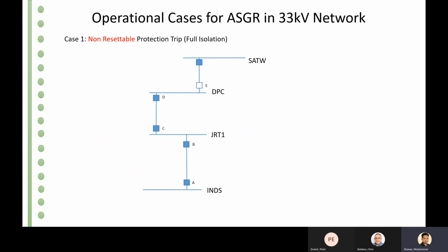So in case of multiple circuit trips, like a circuit from JRT1 and DPC trip, at the same time, INDS and JRT1 also trips, so ASGR will not work for multiple 33 kV circuit tripping. So that'll take just the initial trip. Yes, it will. Initially, our aim is to handle only the simplest trippings. In case of any complex overhead line trippings, the operator will intervene. Okay. That's a one-shot thing. Yes, this is only one shot thing.